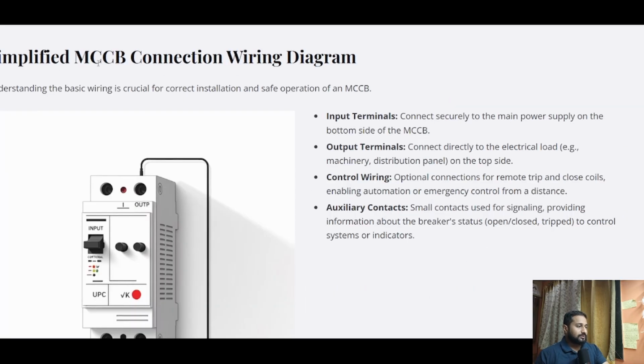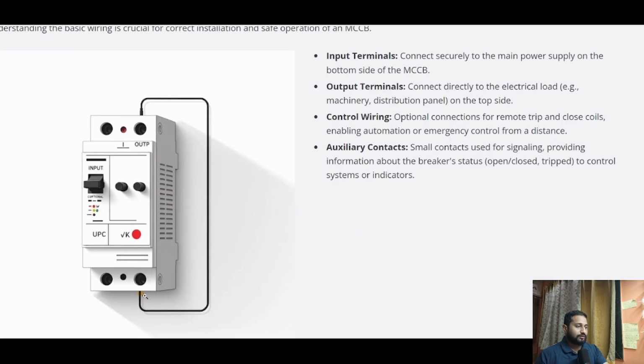Then we have here the simplified MCCB connection wiring diagram. There are input terminals which are connected to the main power supply on the bottom side of the MCCB. So here we have input main power supply. Then we have output terminals which connect directly to the electrical load, that is machinery or distribution panel on the top side. So we have control wiring, which is optional connection for remote trip and close coils, enabling automation or emergency control from a distance. Then we have auxiliary contacts, which are small contacts used for signaling, providing information about the breaker's status, that is on and off, or trip to control systems or indicators. So this is about the connection and physical layout of the MCCB.